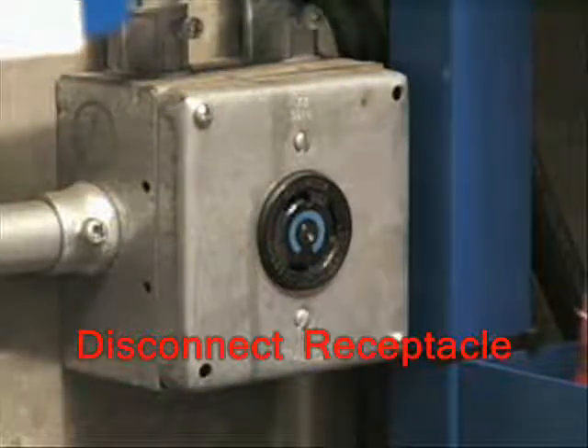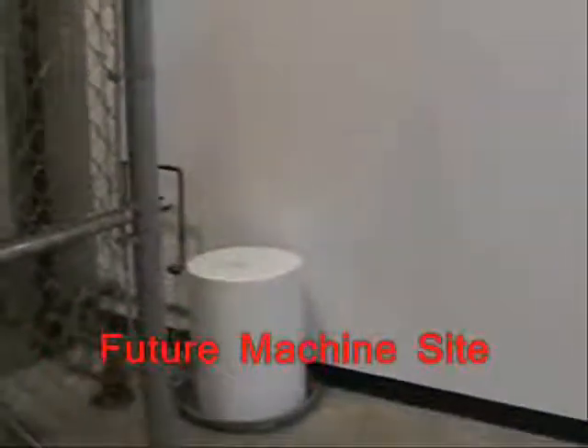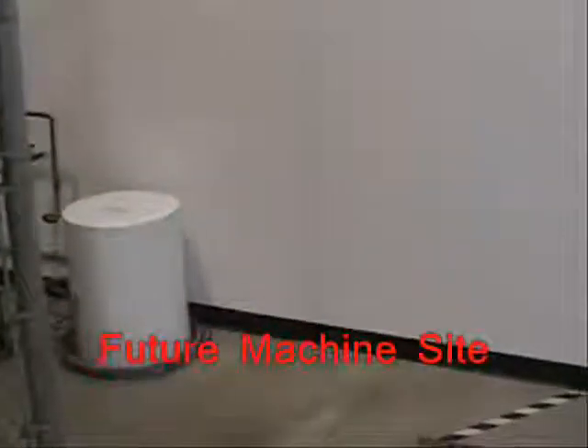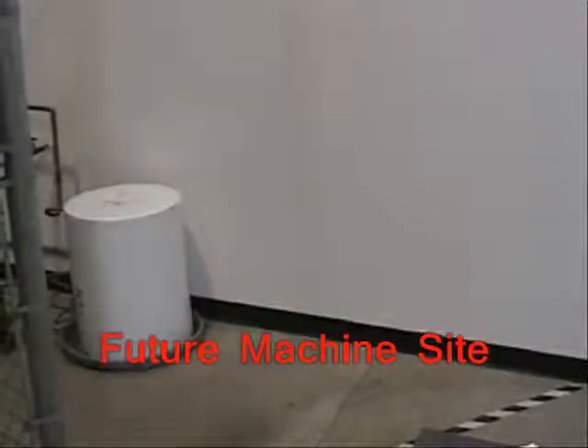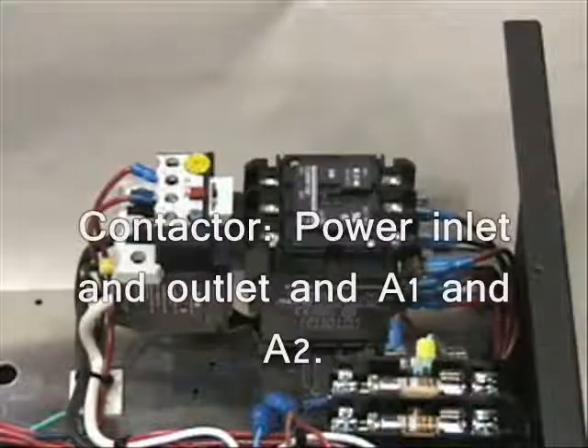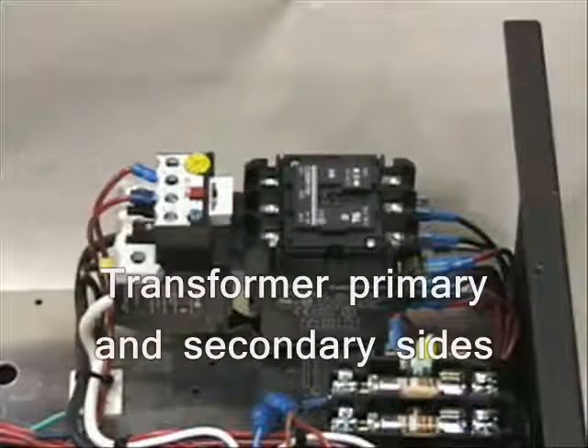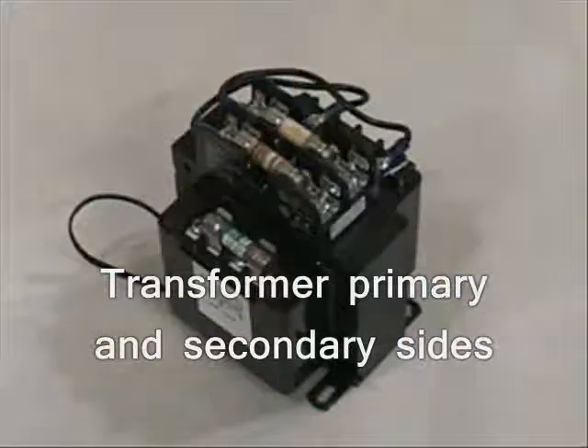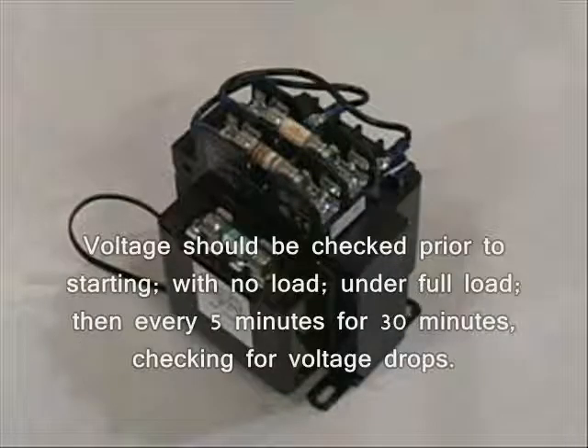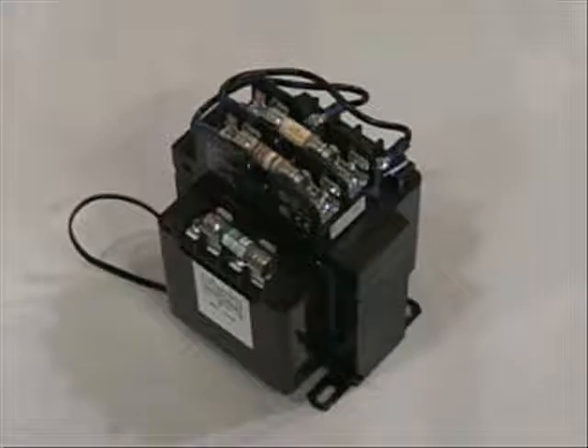disconnect, machine, future site. At the contactor and primary and secondary sides of transformers. Voltage should be checked prior to starting with no load, under full load, then every 5 minutes for 30 minutes to check for voltage drop.